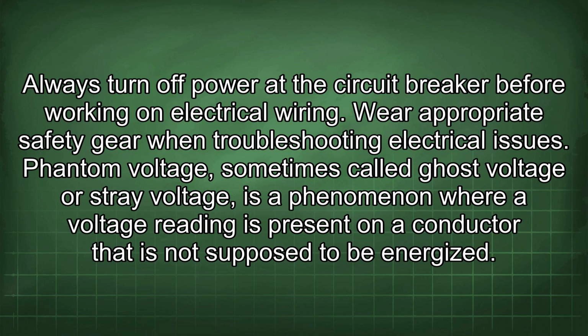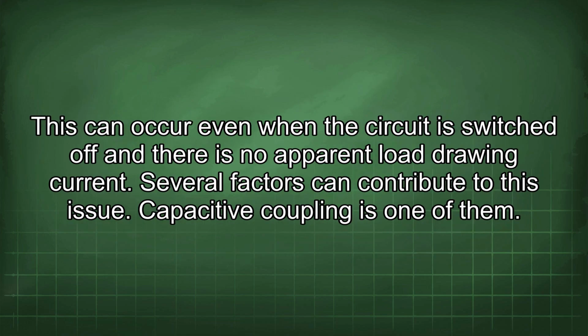Phantom voltage, sometimes called ghost voltage or stray voltage, is a phenomenon where a voltage reading is present on a conductor that is not supposed to be energized. This can occur even when the circuit is switched off and there is no apparent load drawing current. Several factors can contribute to this issue.